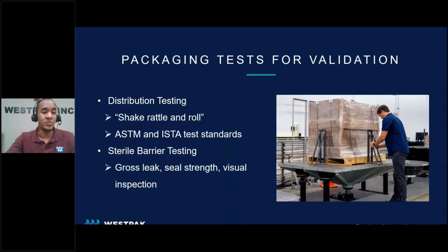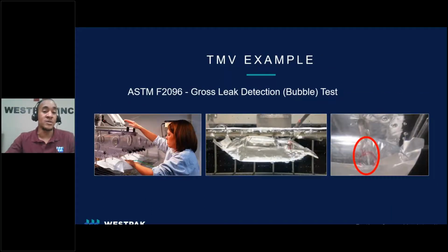So moving on, let's briefly walk through gross leak detection testing and what a TMV actually looks like. Consensus standard ASTM F2096 details gross leak testing. It's a sterile barrier test that involves submerging a sample beneath the water, pressurizing it, and then looking for any breaches that would compromise the sterile barrier. To complete a TMV for this, we define the parameters and the acceptance criteria. We then ensure that the work instructions met the intended purpose of the requirements and of the test standard.